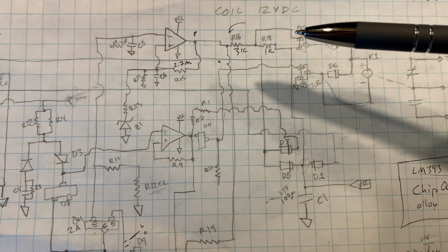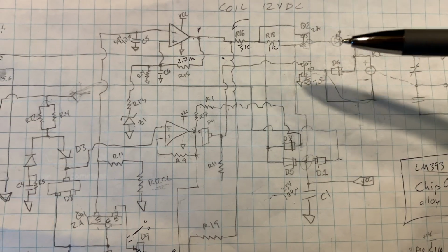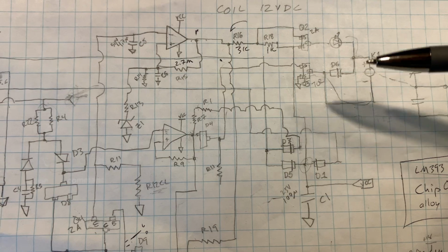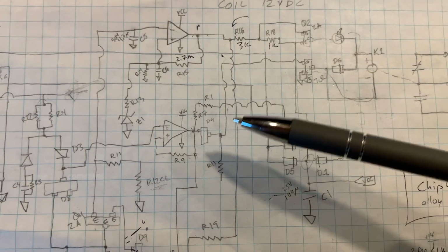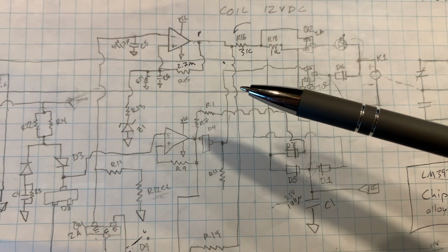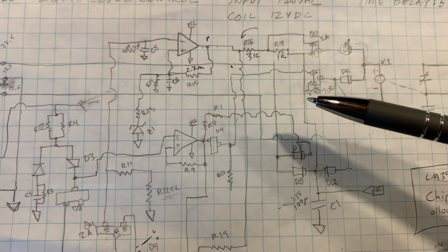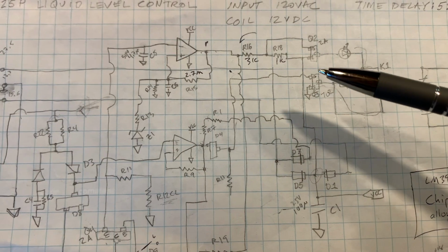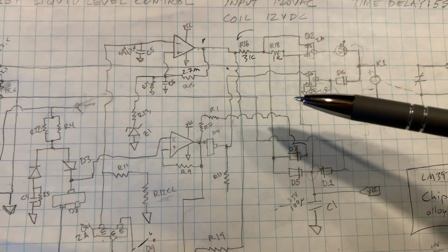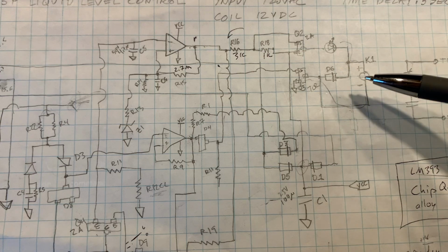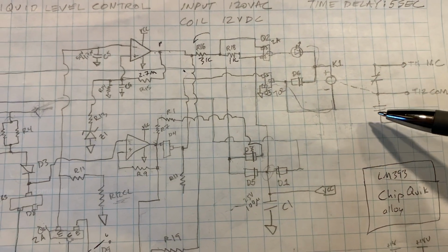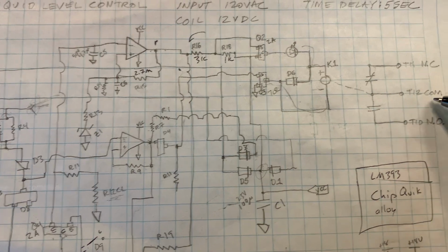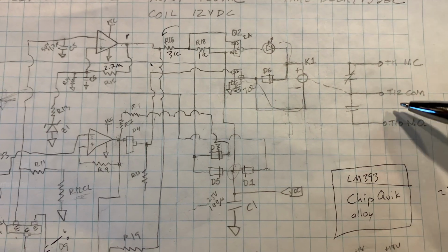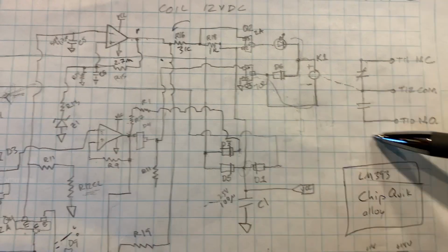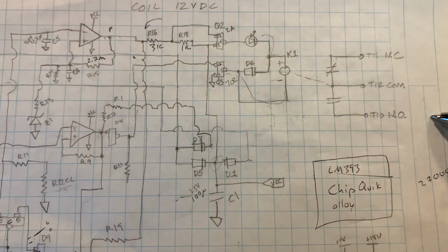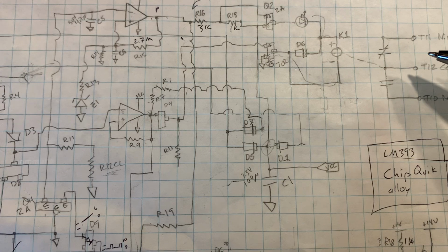I suspect that if this transistor were to short, the relay would stay turned on all the time. So it could be a fail-safe, because it is a safety circuit. Could be a fail-safe that they have this FET that's running here to pull the ground leg of the relay. So as long as the relay is energized, these contacts are closed, and the common and the normally open contacts are closed when the relay is energized, and this goes on to the boiler control module. So that's how it works.